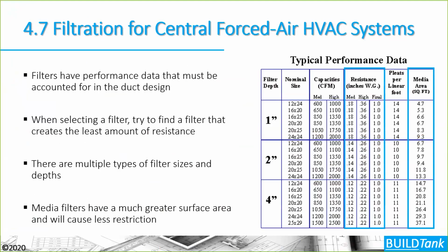You can find filter information in these performance data sheets. However, these performance data sheets aren't easy to find. But if you can find a performance data sheet for the filter brand that you like to use, you can figure out the media square footage of that. On the 4-inch filter, I've got a filter that has 37 square feet of area, and the pressure drop there is minimal. It's less than 1. So picking the right filter makes a lot of sense here, and a higher MERV rated filter as well.